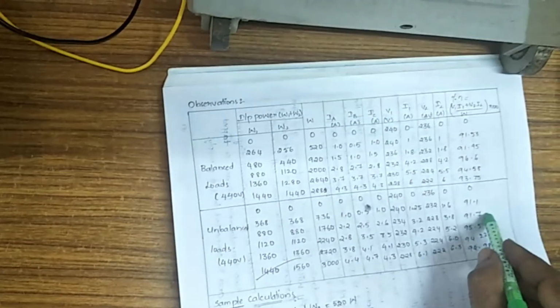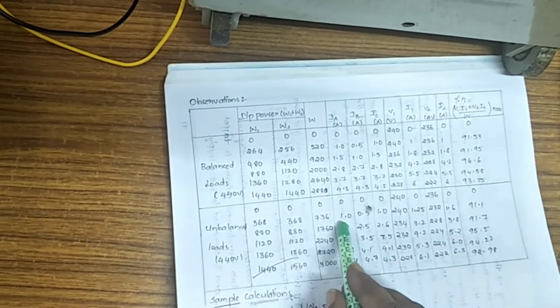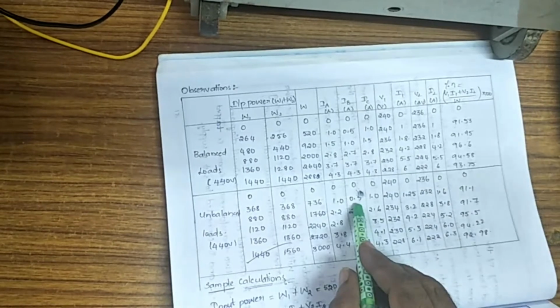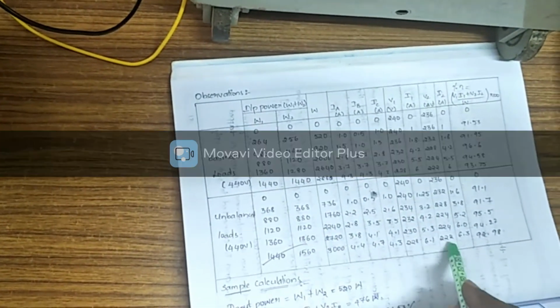So this gives you what? For unbalanced load conditions, if you see here, current IA is 1 ampere, IB is 0.5 and IC is 1. So all are different. Unbalanced loads you can consider. So for unbalanced loads also you have to find out the efficiencies. This is how the tabulation of the parameters is done, and the calculation is very simple.